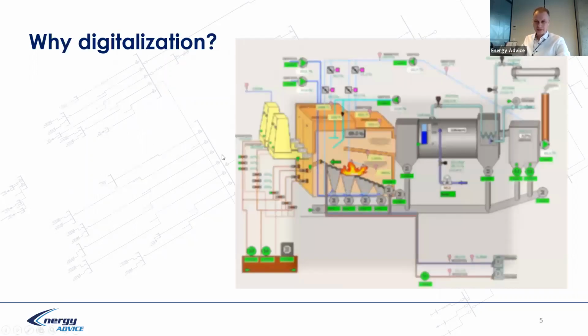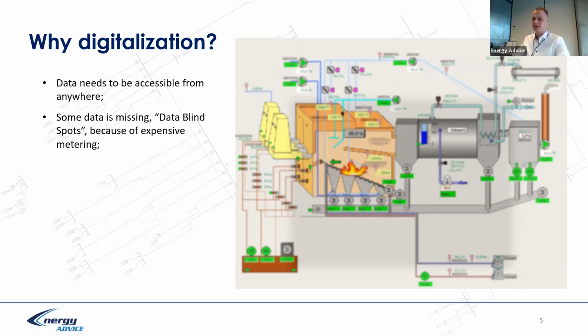Why digitalization for biomass boilers? Because people are telling us that they need to access data from anywhere, maybe from home, maybe from their office, and not go to the boiler house. Some data is missing, data blind spots because of expensive metering. For example, if we are willing to measure flue gas flow or air flow, we need flow meters. However, flow meters in general suffer from the environment, and because they suffer from the environment, the measurement error probably is unacceptable during the lifetime, and we need to recalibrate metering devices.